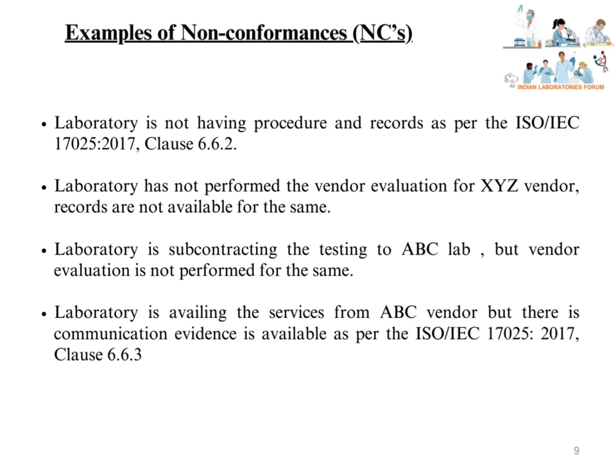Some examples of non-conformances as per Clause 6.6: The laboratory does not have a procedure and records as per ISO/IEC 17025:2017 Clause 6.6.2. The laboratory has not performed vendor evaluation for XYZ vendor and records are not available. The laboratory is subcontracting testing to ABC Lab but vendor evaluation has not been performed. The laboratory is availing services from ABC vendor but no communication evidence is available as per ISO/IEC 17025:2017 Clause 6.6.3.